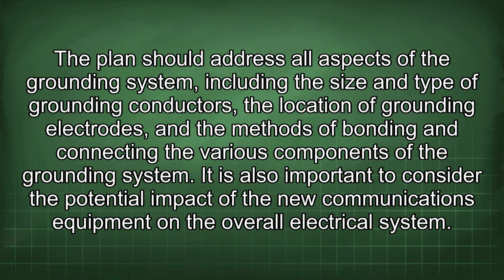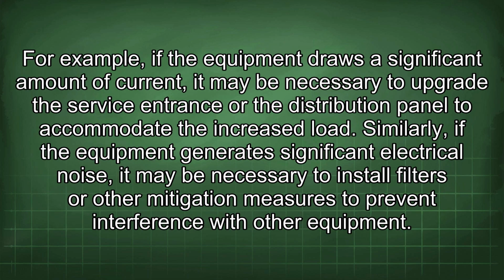It is also important to consider the potential impact of the new communications equipment on the overall electrical system. For example, if the equipment draws a significant amount of current, it may be necessary to upgrade the service entrance or the distribution panel to accommodate the increased load. Similarly, if the equipment generates significant electrical noise, it may be necessary to install filters or other mitigation measures to prevent interference with other equipment.